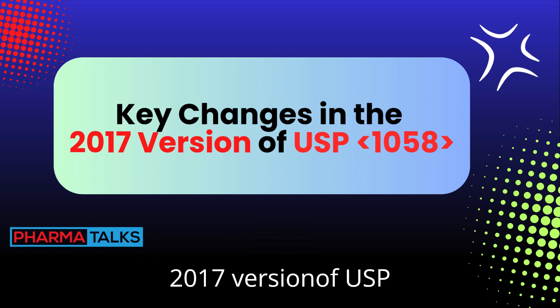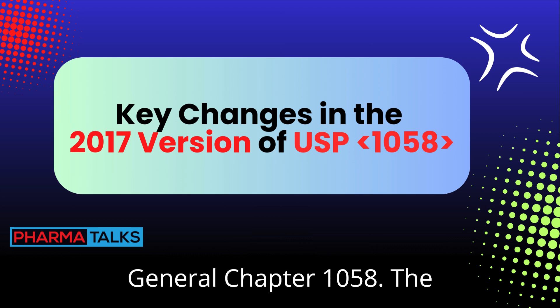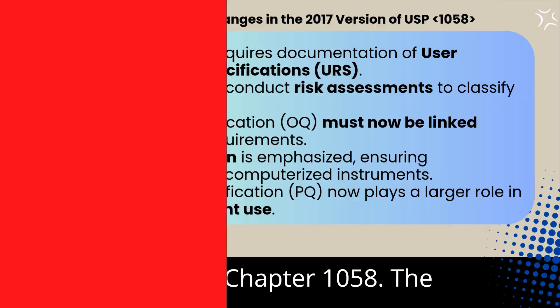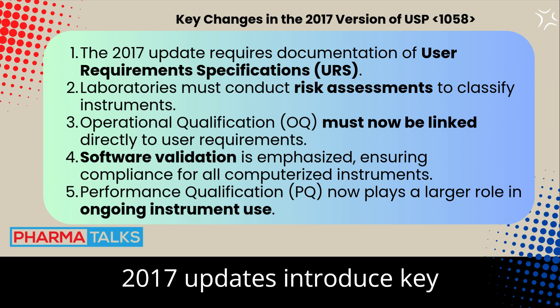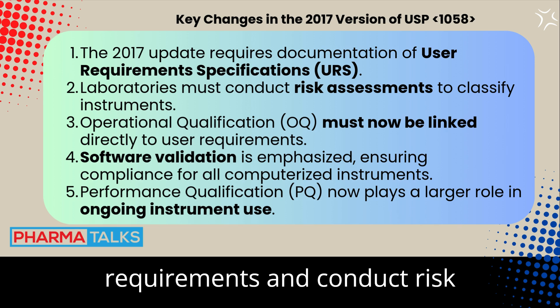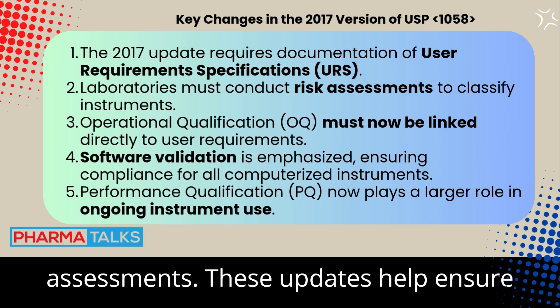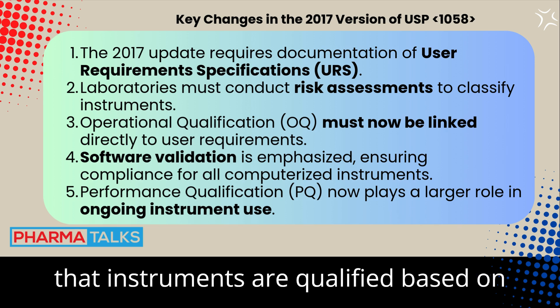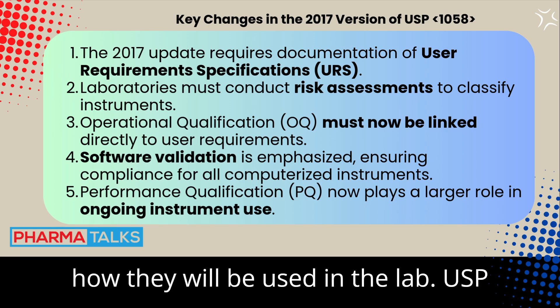The 2017 updates to USP General Chapter 1058 introduce key changes, like the need to document user requirements and conduct risk assessments. These updates help ensure that instruments are qualified based on how they will be used in the lab.